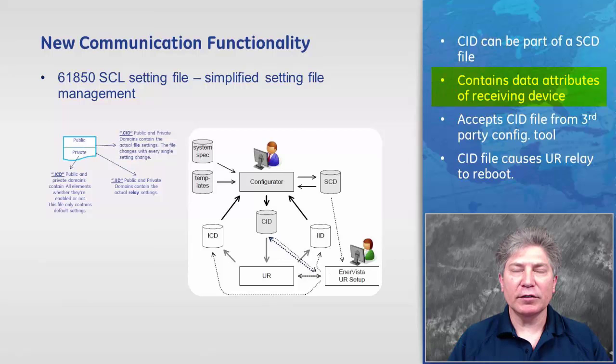It will also accept a CID file from a third-party configuration tool, provided that that CID file is derived from a UR ICD file and contains the elements of the ICD file. When a UR relay receives a CID file, it will reboot as well.